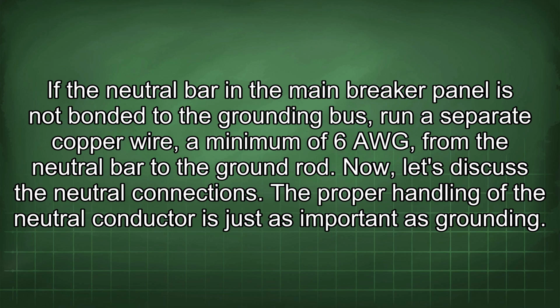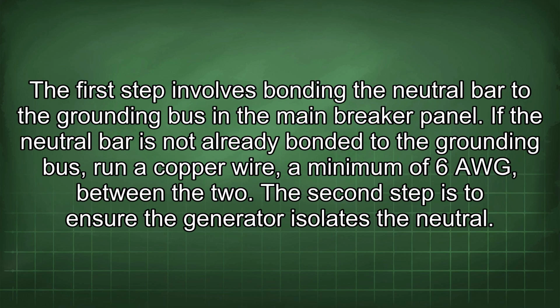Now let's discuss the neutral connections. The proper handling of the neutral conductor is just as important as grounding. First step involves bonding the neutral bar to the grounding bus in the main breaker panel. If the neutral bar is not already bonded to the grounding bus, run a copper wire, a minimum of 6 AWG, between the two. The second step is to ensure the generator isolates the neutral.